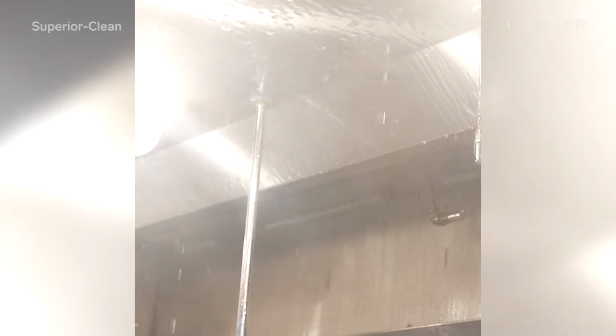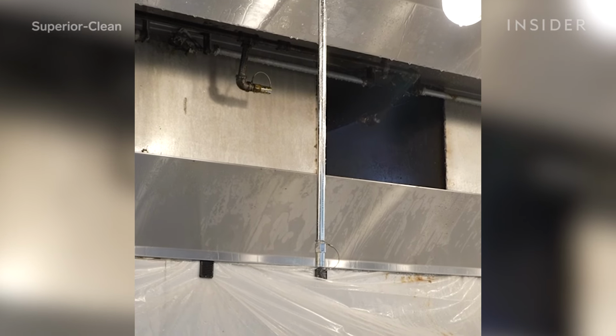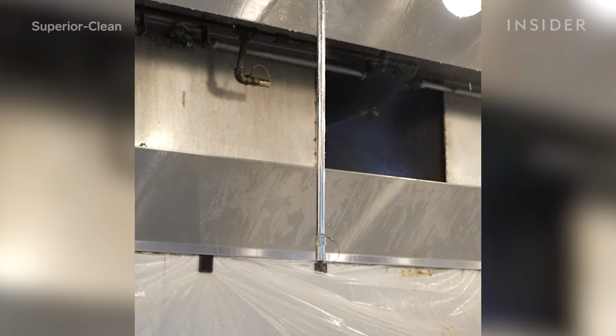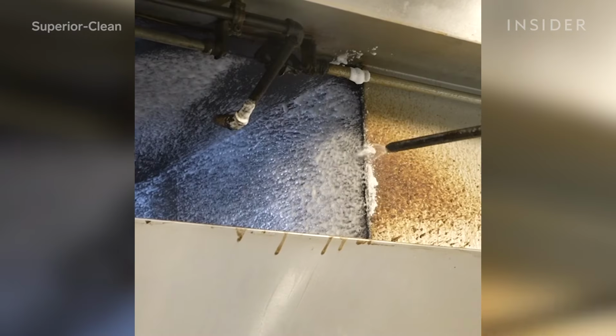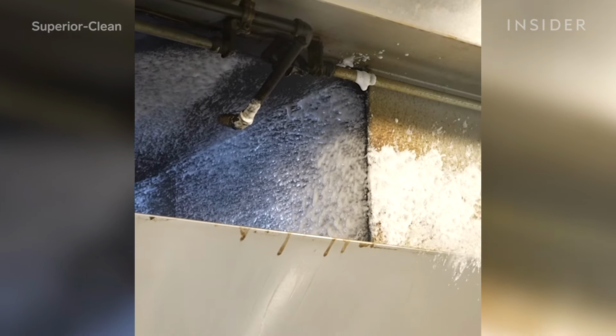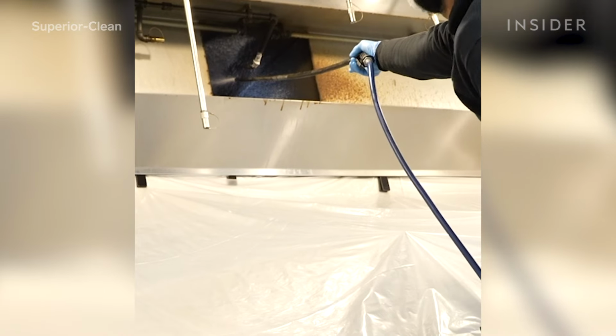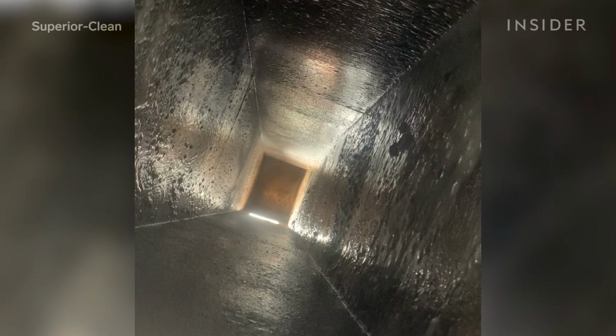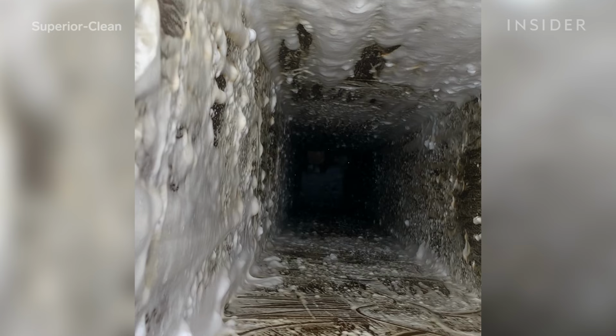Now that we have flushed the entire ductwork back into the kitchen, we are able to apply a low pressure, high steam rinse of the kitchen hood. So the opening to the ductwork in the hood system starts behind the hood filters. The way we clean this is exactly as the rest of the system. We do not neglect any areas of the duct. This needs to be degreased, scraped, and steam cleaned.